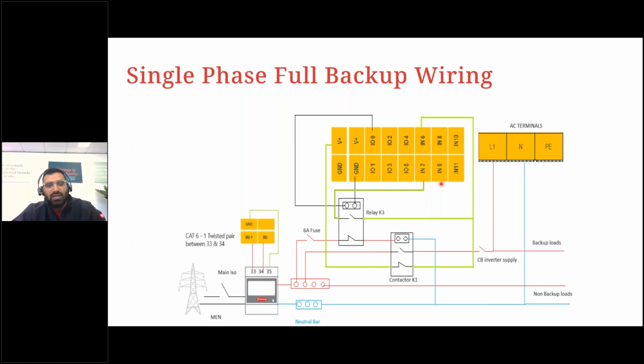So when the inverter has this feedback from IN6 and IN7 coming from the contactor and relay respectively, the inverter knows that the contactor and relay have worked, and we can now go into backup scenario. But provided there are also some other conditions we need to satisfy before the inverter goes into backup. So one of them is that there shouldn't be any power supply to the meter, so the actual smart meter should be turned off, or there should not be any power supply or AC connection readings coming at the inverter AC clamps. So if the inverter gets AC readings on the AC clamps from the grid, it knows that the grid has not gone, and it will not switch into backup.